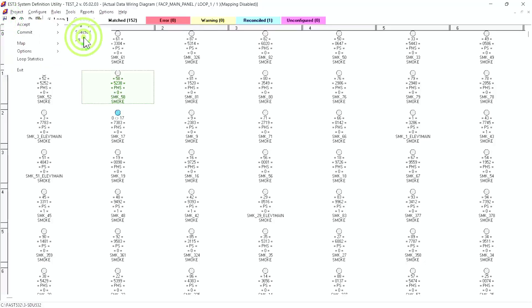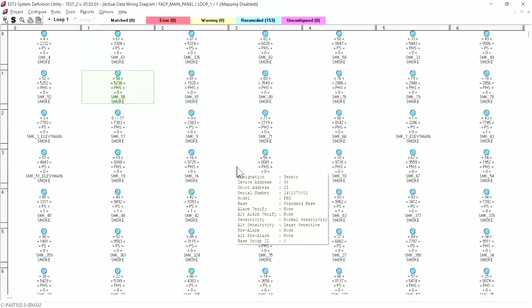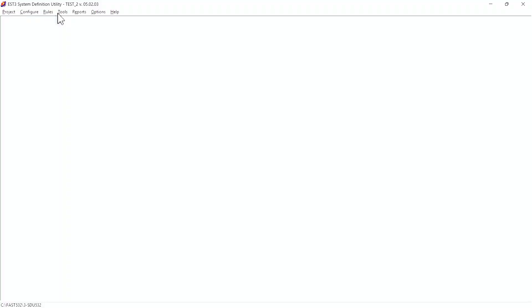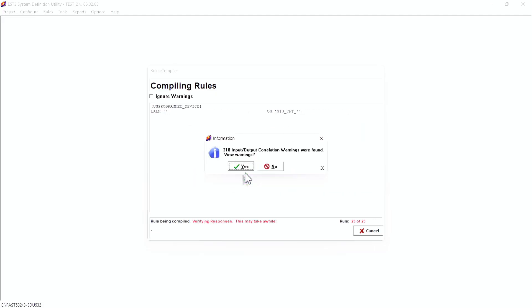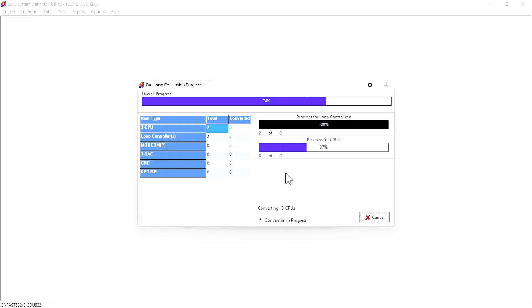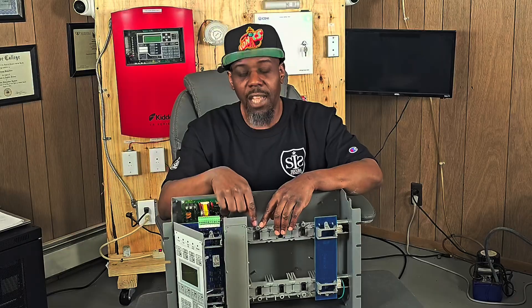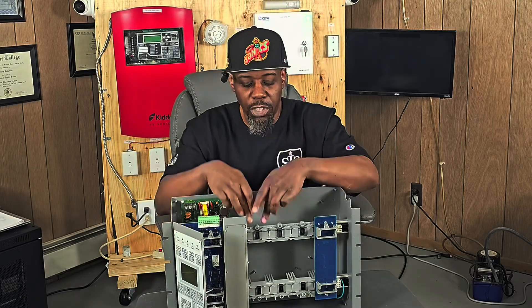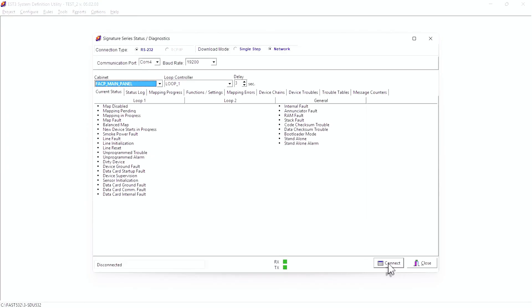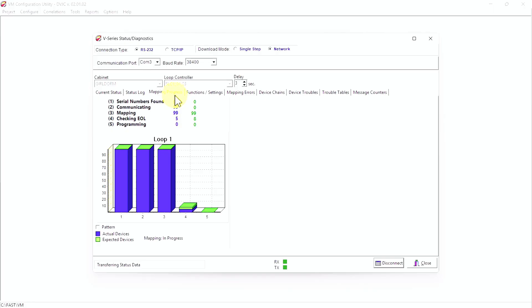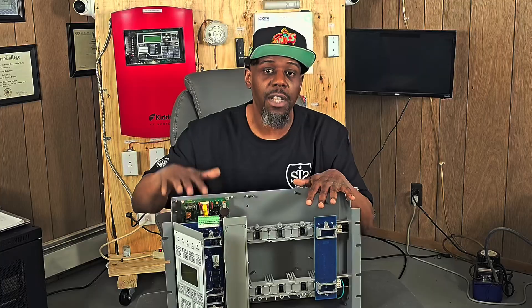What you want to do is: once you upload the loop, you want to commit the expected — that whole tree. Once you commit that whole tree, each icon would turn blue to let you know that you've made some changes. Then you go and compile — you compile all of your loop controller databases, or just the one you're working on, depending on how many map faults you have. You compile that information and then download back to that loop controller, because what you're telling the system is that the software has a good map. Now redesign this map so we can clear this map fault. Once you download, make sure you diagnose your status. Go to your status and diagnostics, connect to the loop card, and wait for the system to actually map all the way and wait for the map to complete. Once the map is complete, you have one more step: upload that complete map so that everything in the software and everything in the field is the same.